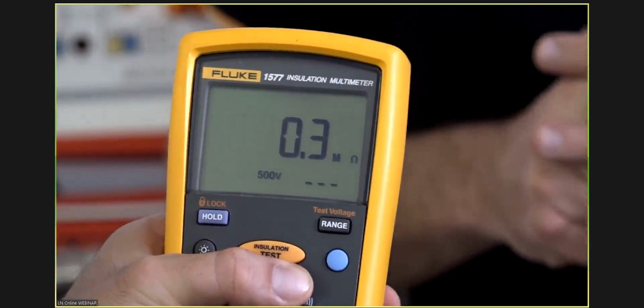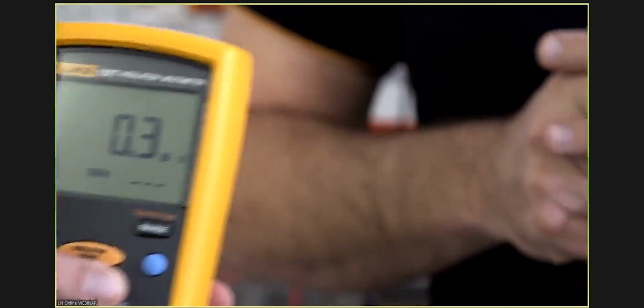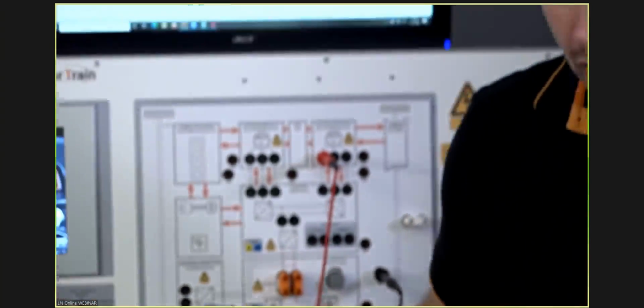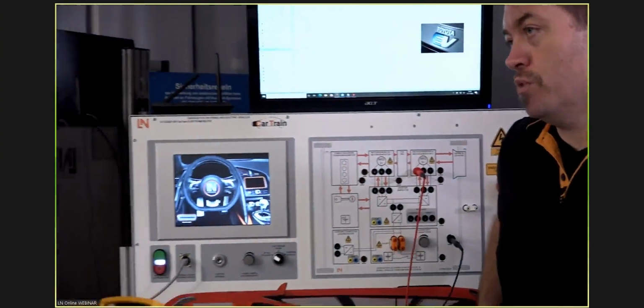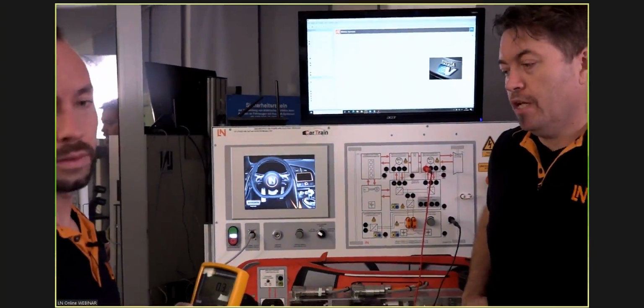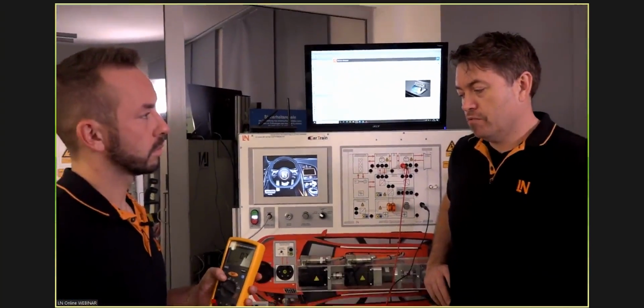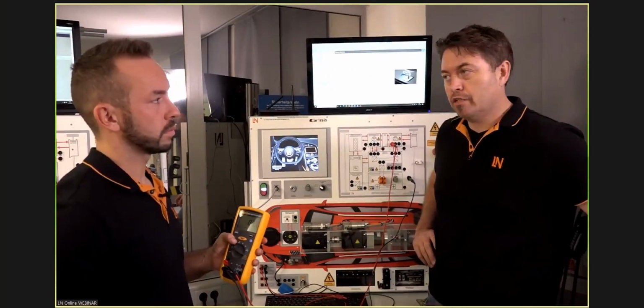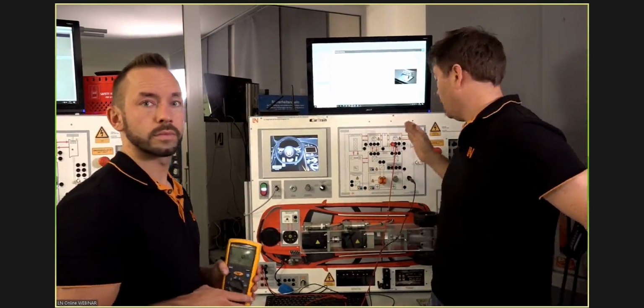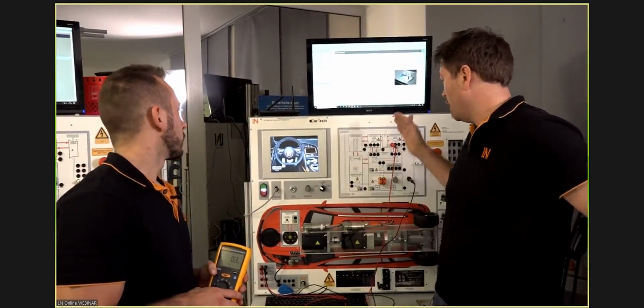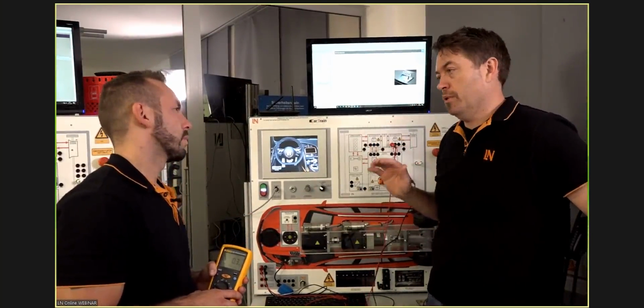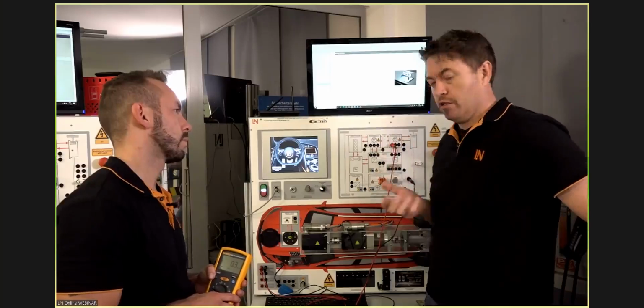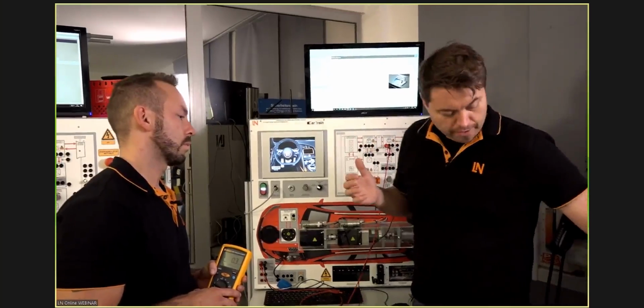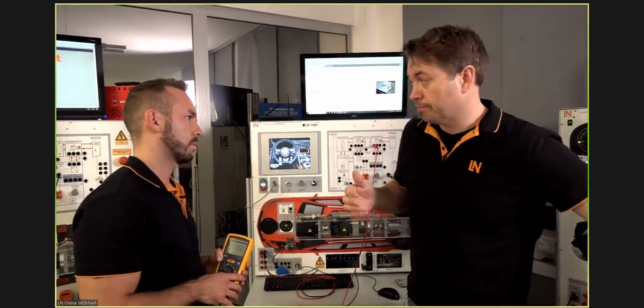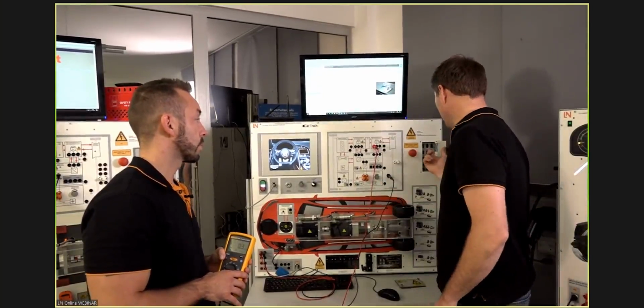There is a formula for working it out. I think each volt needs 1,000 ohms or something like that. Yeah, so that's not enough. That's actually leaking out because we've put a fault there. But that's then showing the student, okay, they've done the test, they've done the shutdown, and they've identified where the problem is. Exactly. So we're not about repairing the system here. It's about understanding and doing the fault finding. Absolutely.